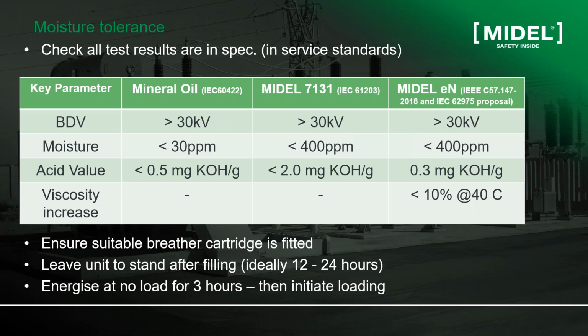And of course, once you do the retrofill, you need to plan continuous maintenance of that transformer. For that, we need to educate our maintenance engineers on the differences in the in-service limits between mineral oil and esters. In the table in front of you, you can see 3 or 4 parameters. These are the basic parameters to check. One is the breakdown voltage. Esters and mineral oil are equivalent in that term, and the breakdown voltage should be higher than 30 kV. For the moisture content, mineral oil is very sensitive to moisture, so it will not tolerate any moisture above 30 ppm. Then you need to do maintenance on the liquid.